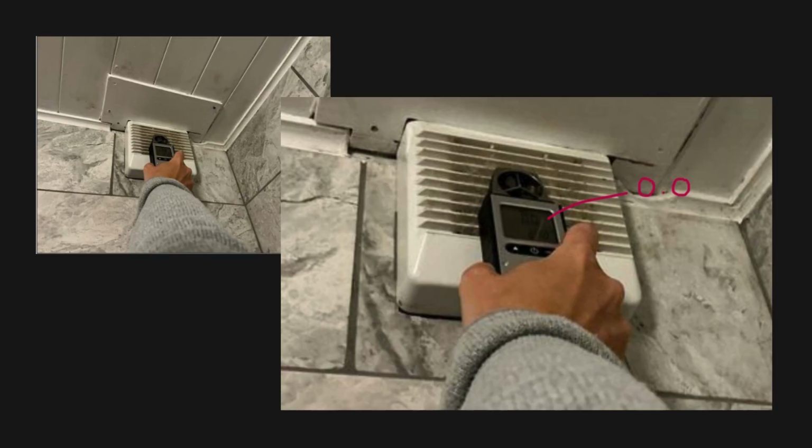So this bedroom is adjacent to the bathroom, and in the bathroom there's an extractor fan. Normally within a level 2 survey we'd be commenting on whether it appears to work and whether it appears to be ducted to outside air. I couldn't see anywhere that it was ducted. I think that the vent that I could see related to the boiler. I turned the fan on and it did make a noise, but something didn't quite feel right, and I could feel that there didn't seem to be a lot going on, even though it was making all the right noises.